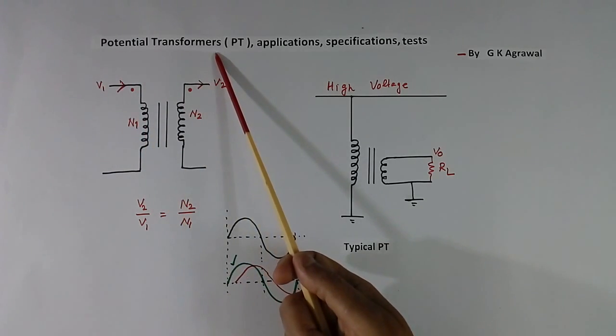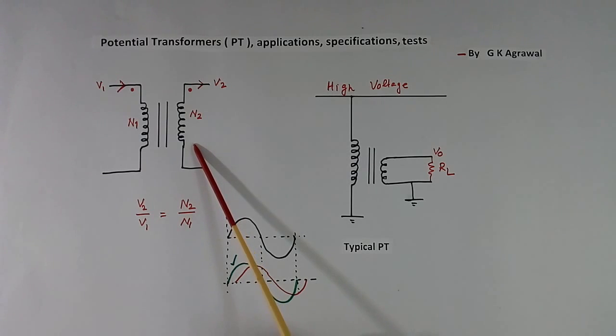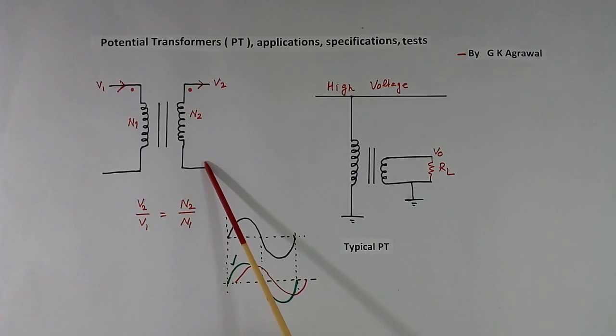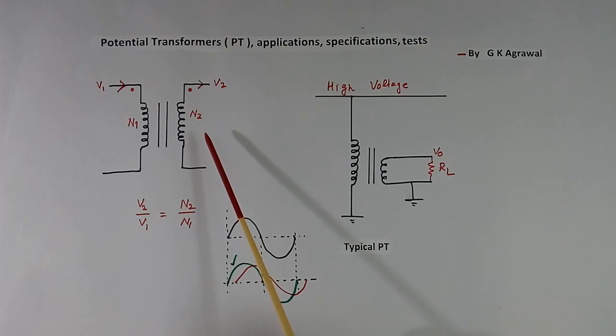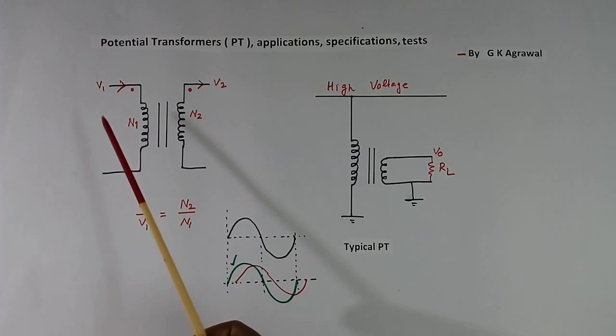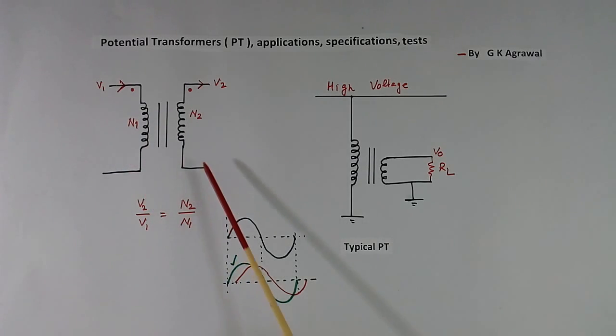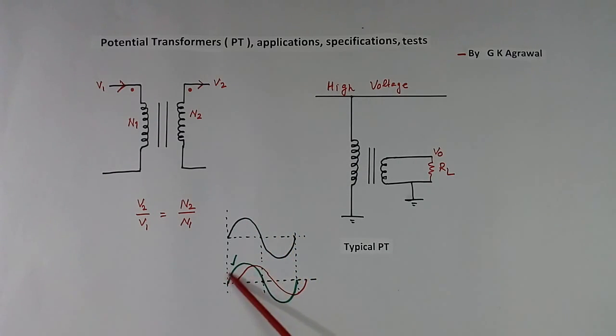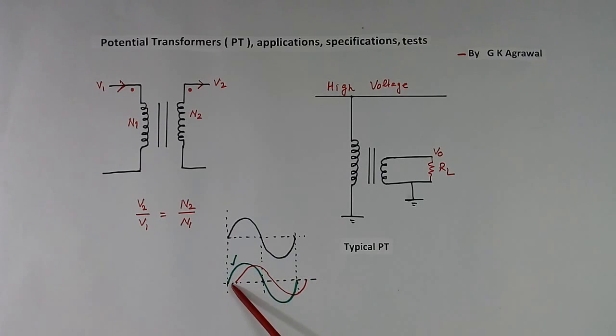A potential transformer is a step-down transformer which provides voltage in the secondary in correct magnitude and phase. Correct magnitude means the secondary will be proportional to the primary. Correct phase means there is no phase shift between primary and secondary voltage. As shown here, the green color is correct because there is no delay or phase shift, but the red color is not okay — there is a phase shift present.